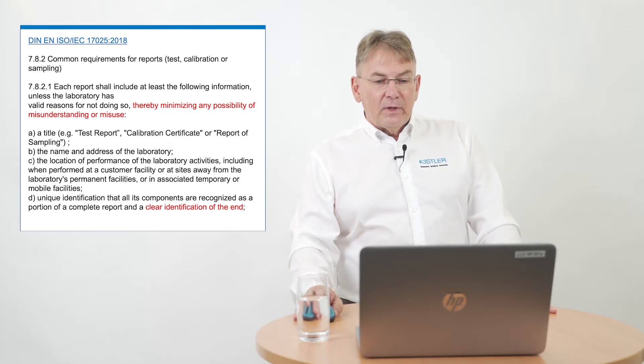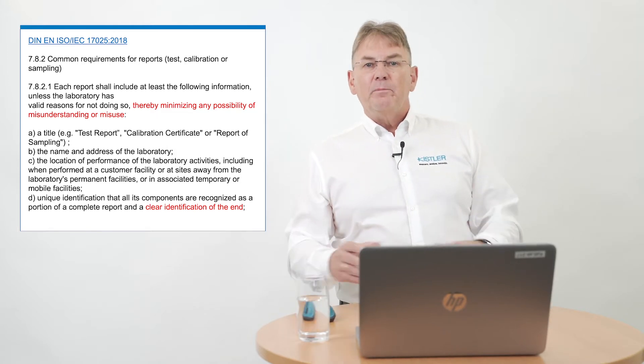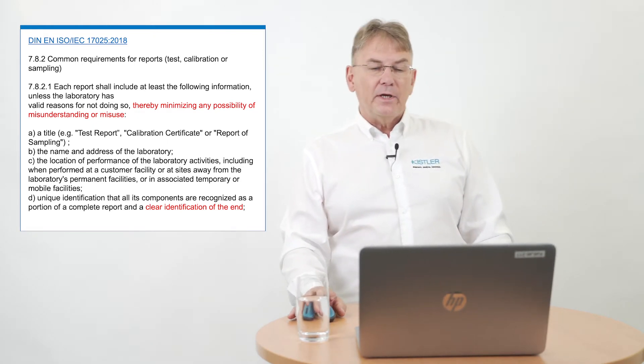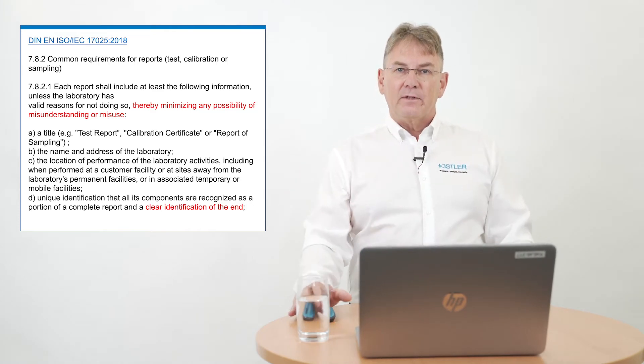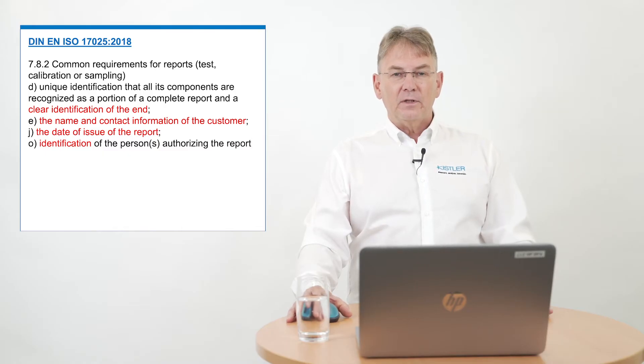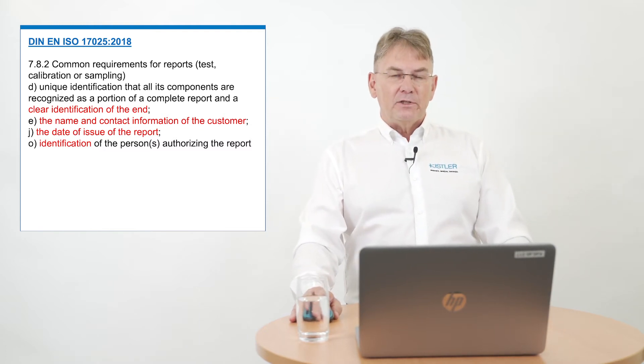Something very new is a clear identification of the END. In former calibration certificates you probably have seen 'page 3 of 3' or 'page 2 of 3.' Right now, there must be a clear identification of the END, like 'End of Certificate.' They want to prevent additional information from being added to the certificate. You also need to find the name and contact information of the customer. Sounds silly, sounds very common — but even big companies change their names so often. Please check: it's your calibration certificate and you have to insist on the proper name.